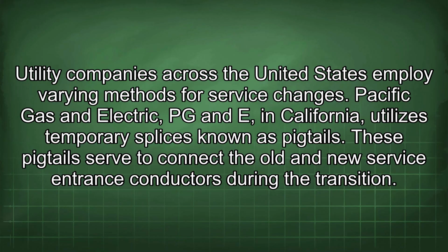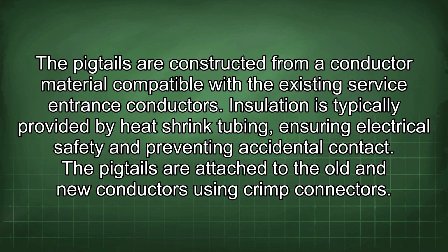Utility companies across the United States employ varying methods for service changes. Pacific Gas and Electric (PG&E) in California utilizes temporary splices known as pigtails. These pigtails serve to connect the old and new service entrance conductors during the transition. The pigtails are constructed from a conductor material compatible with the existing service entrance conductors. Insulation is typically provided by heat shrink tubing, ensuring electrical safety and preventing accidental contact.